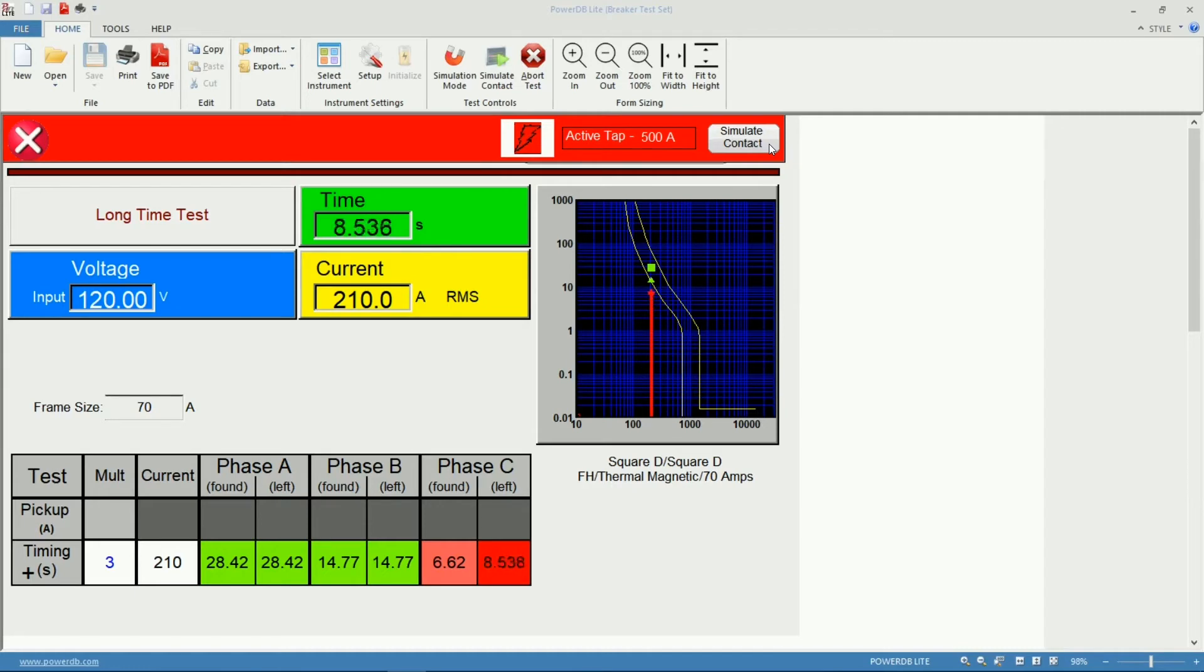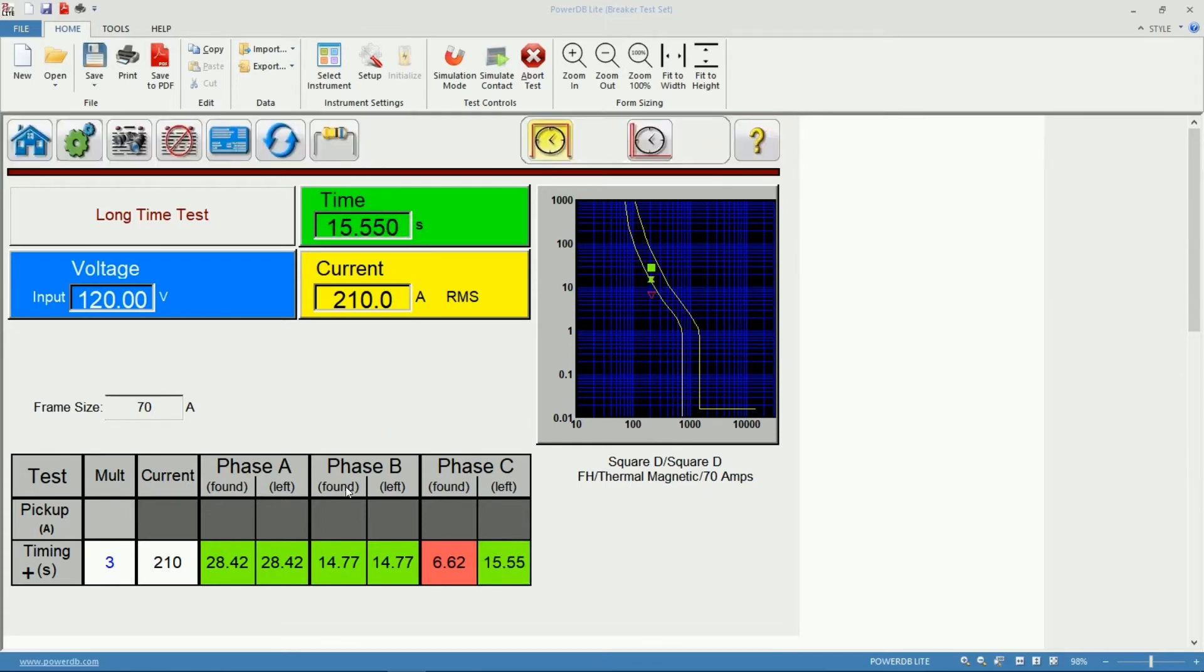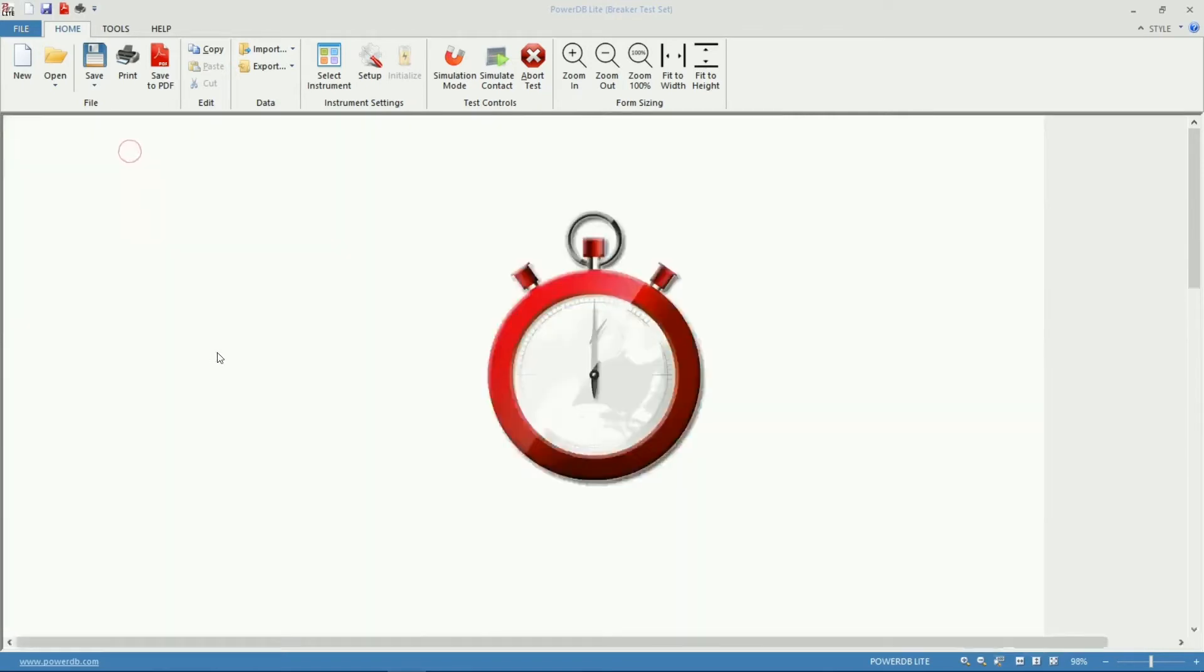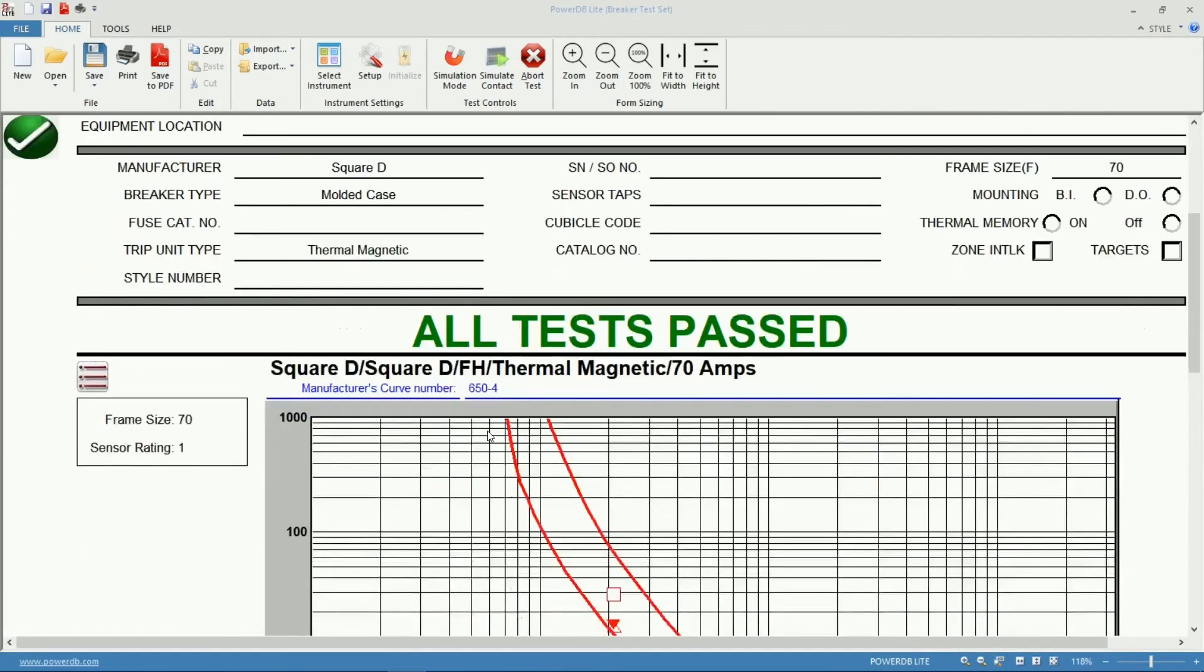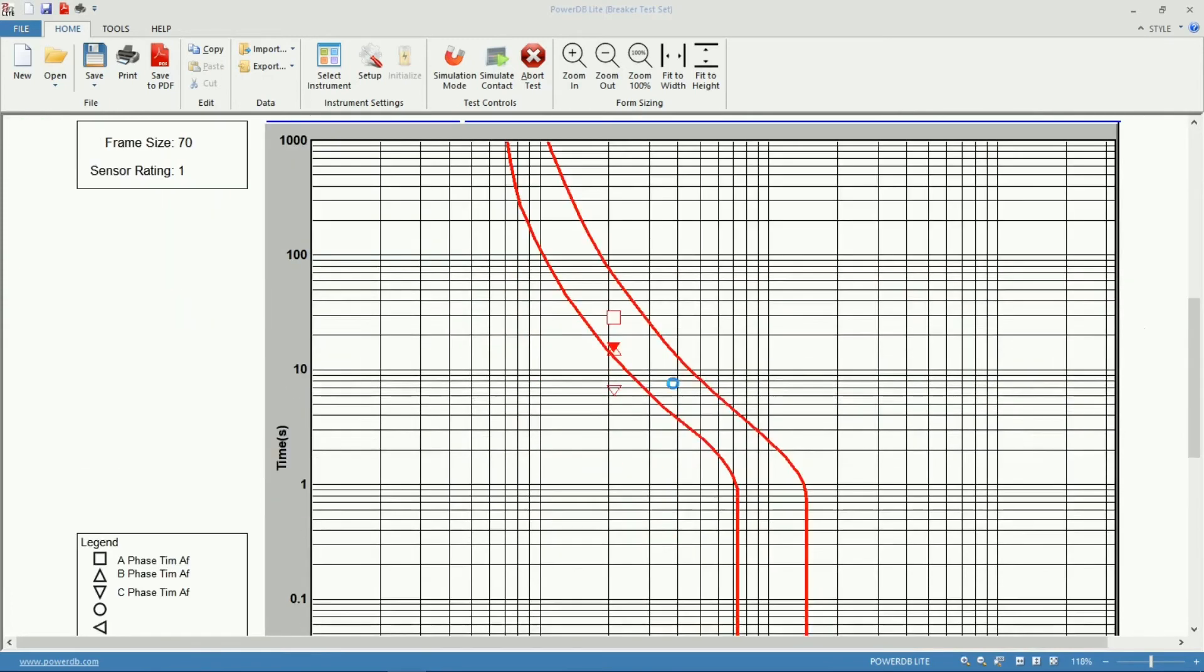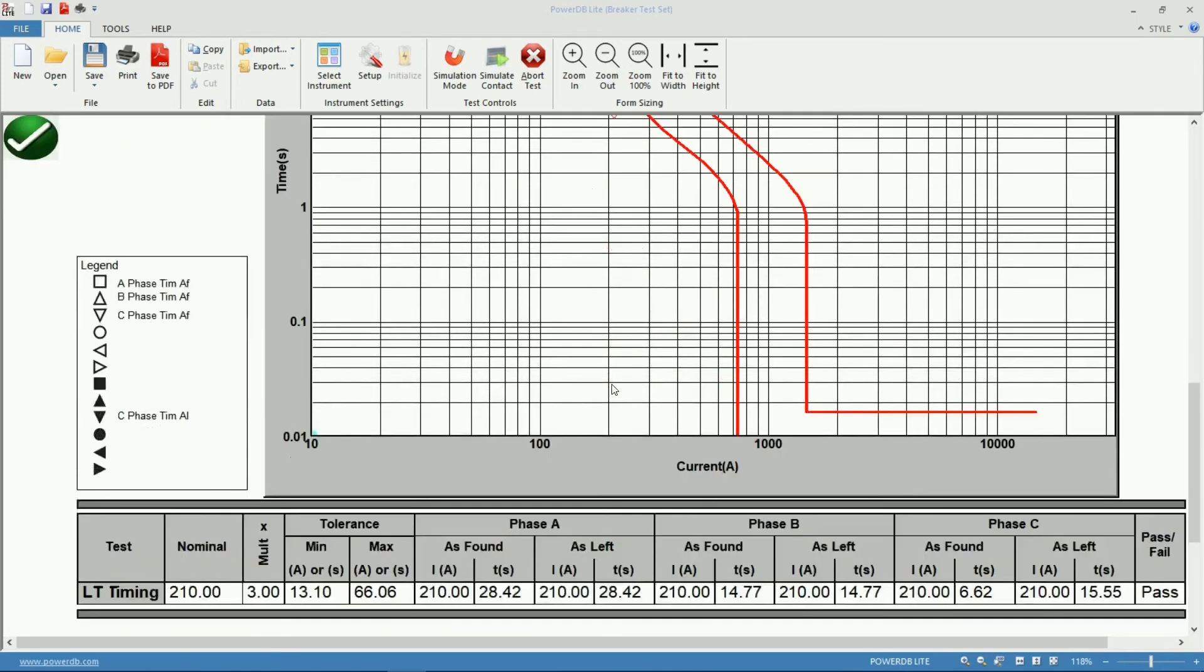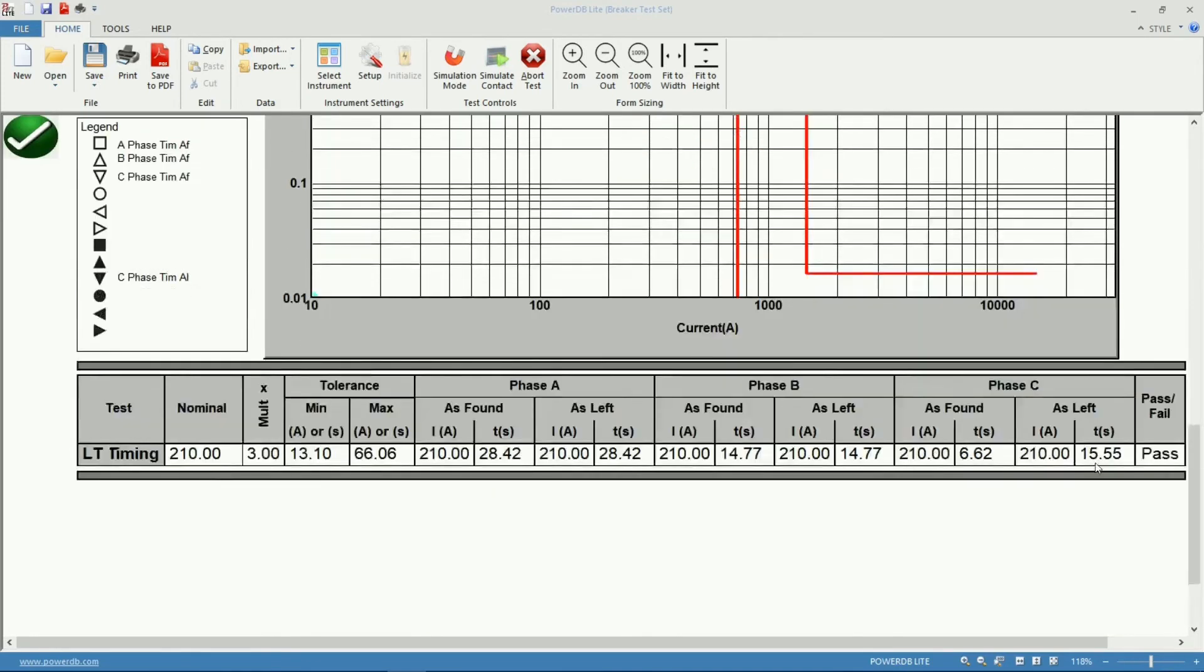In this case I'm going to simulate the trip inside the limits so now all three phases are within the limits specified by the manufacturer. We have green there. Let's go back to our report. Now all tests passed and we're not erasing our previous reading where we found that phase outside limits, we still have those readings in our report.